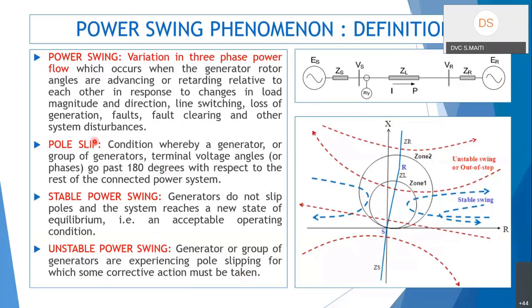Pole slip is a term used when a generator or group of generators has terminal voltage angles that go past 180 degrees apart with respect to the rest of the connected power system. In the R-X plane, stable swings come in and return back without crossing the negative resistance axis.